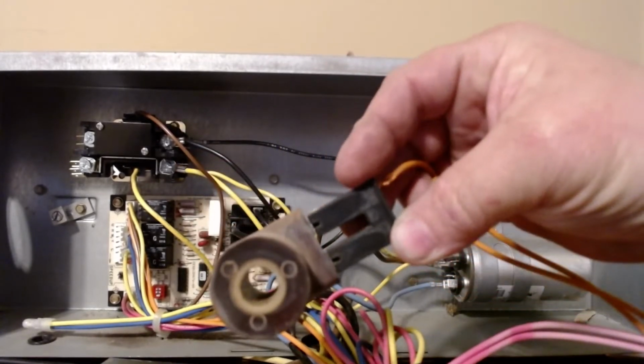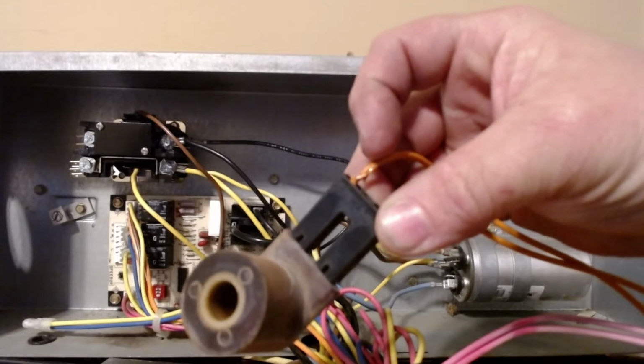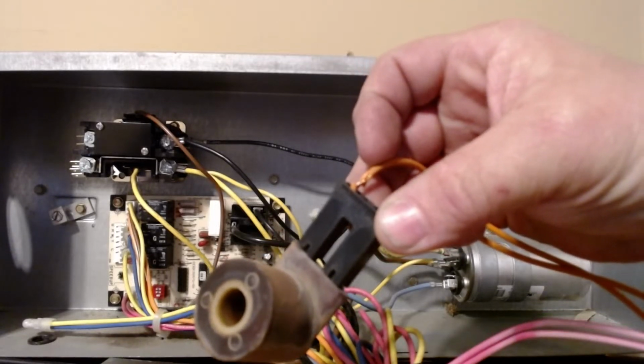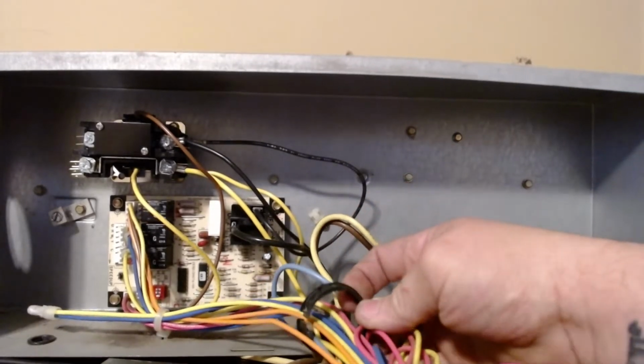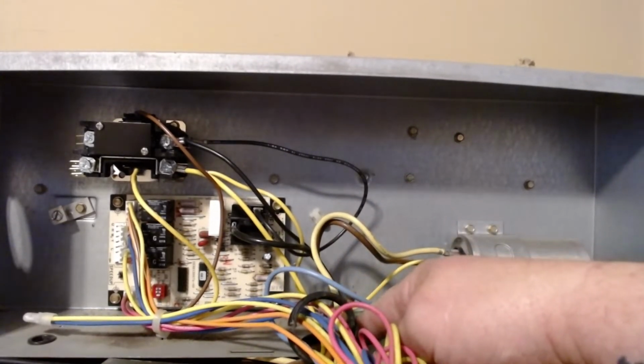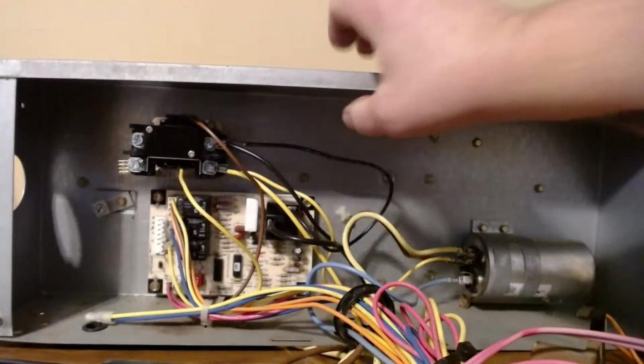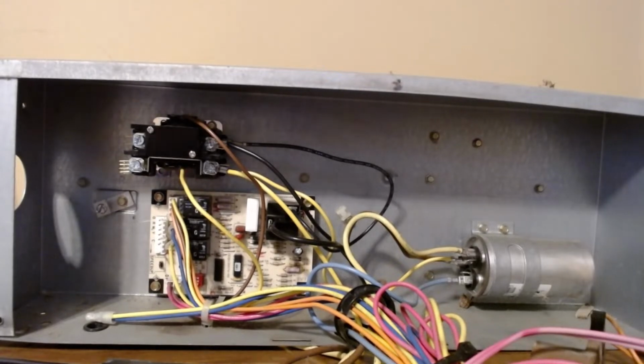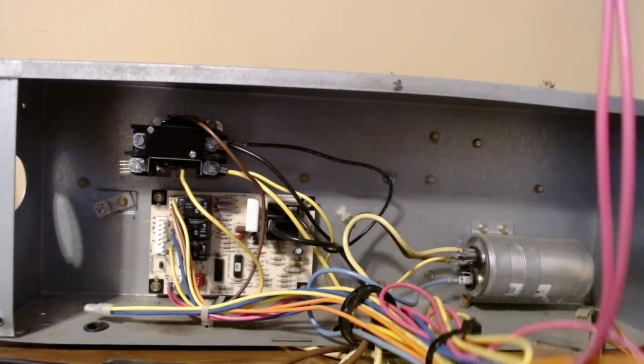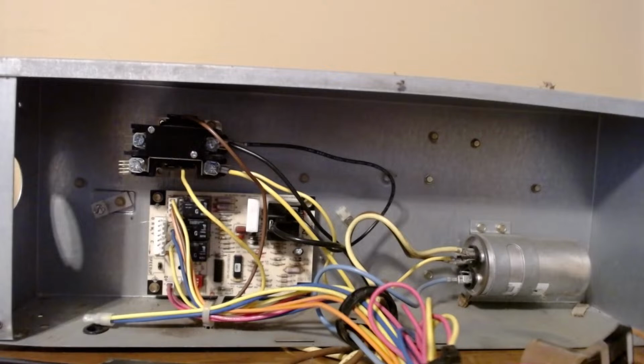And here's a very worn reversing valve magnetic coil. You can see the bare wire there. That happened in transport. And Carrier likes to put this beautiful black ring where it goes to the bottom of the casing here to prevent any kind of wire rubbing. Some other manufacturers take it through the cabinet and don't put any protection on there, and you'll get wire rubs on the metal and everything else. Also, these wires, when they sit up against copper pipes, they can rub and everything else.